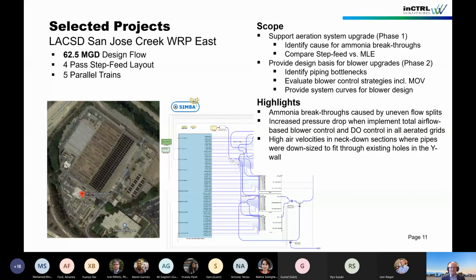The other thing we found was where the high air velocities were, and in this case the big ones were in what they call neck down sections. The plant was built in 1969, and there were existing holes through the walls between passes. When they upgraded over the years, they reused these holes to put some new piping through, so they had to neck down to a smaller diameter to fit through these existing holes, and then expand back out again when they connect with the drop leg.